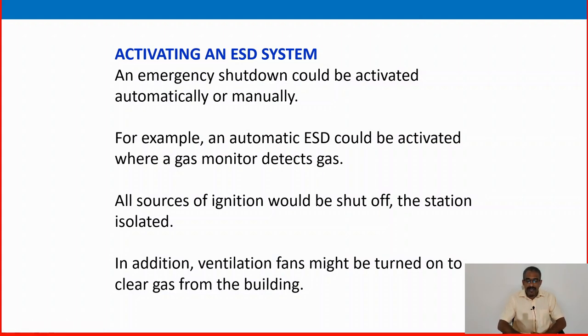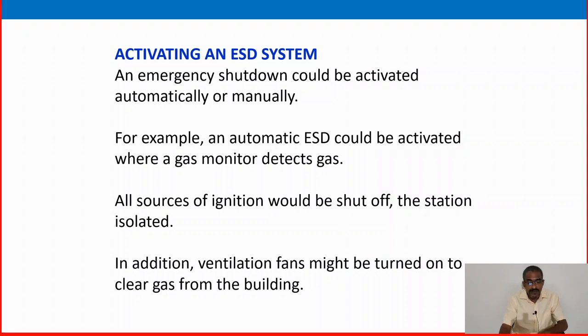For example, an automatic ESD could be activated where a gas monitor detects gas — all sources of ignition would be shut off and the station isolated. In addition, ventilation fans may be turned on to clear the gas from the building.